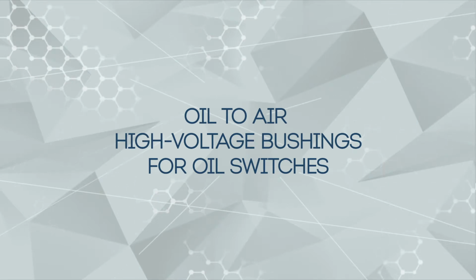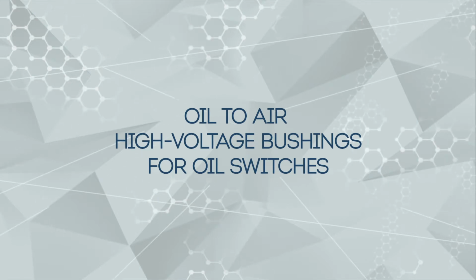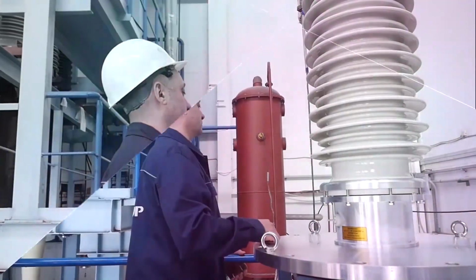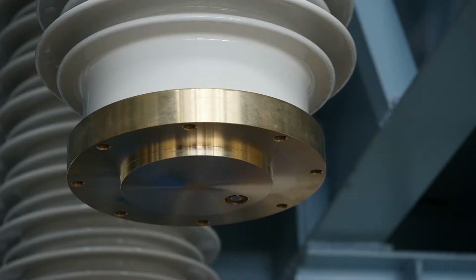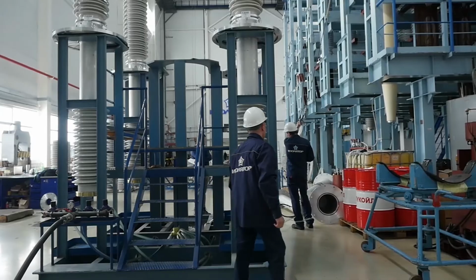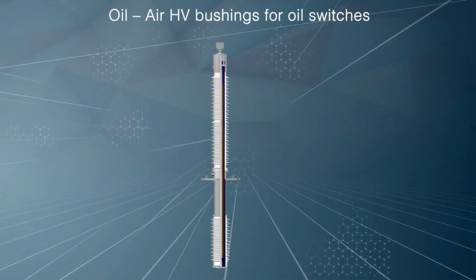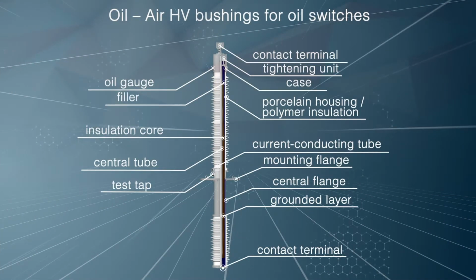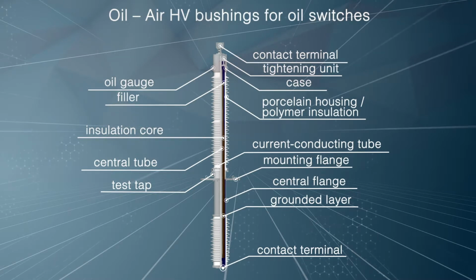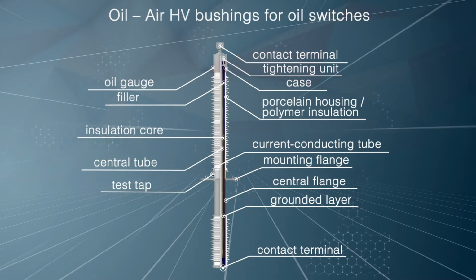Oil-to-air high-voltage bushings for oil switches. Bushings are the main insulating element of the oil circuit breaker, ensuring its reliable and secure operation. The polymer external insulation is used as an alternative to porcelain insulation on 110 and 35 kilovolt bushings. The type of connection of 35 kilovolt bushings depends on the type of the circuit breaker which they are installed on. Connection of 110 and 220 kilovolt bushings is done with the help of a contact tip screwed on the central current conducting element of the bushing.